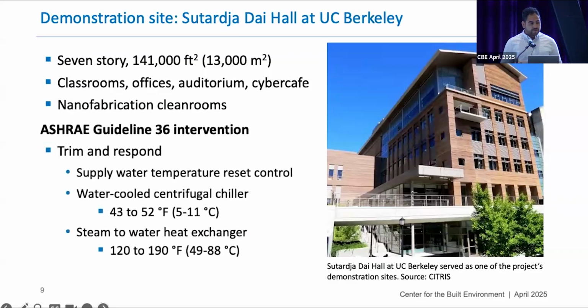So due to these constraints, the only control block that we were able to implement from Guideline 36 was the trim and response block. We implemented the Guideline 36 intervention in both the chilled and hot water plants. But today I'm just going to focus on the chilled water plant. The chilled water plant uses a water-cooled centrifugal chiller with 24-hour operation because of the nanofab. So there's cooling loads all the time in this building. And the trim and response modifies the chilled water supply set point from 43 all the way up to 52 degrees, depending on the chilled water demand.